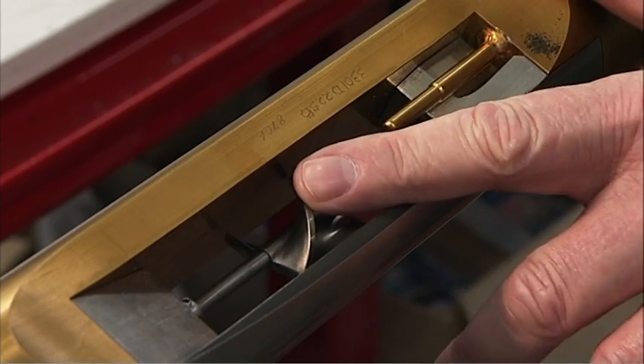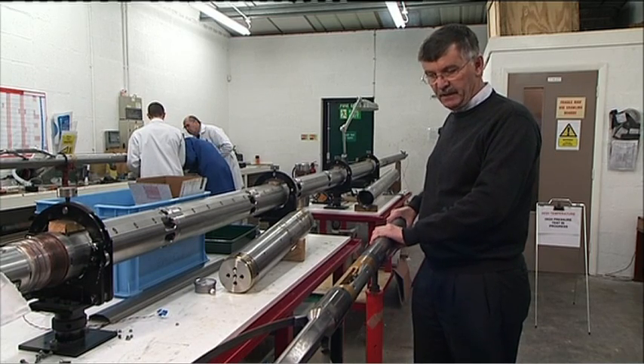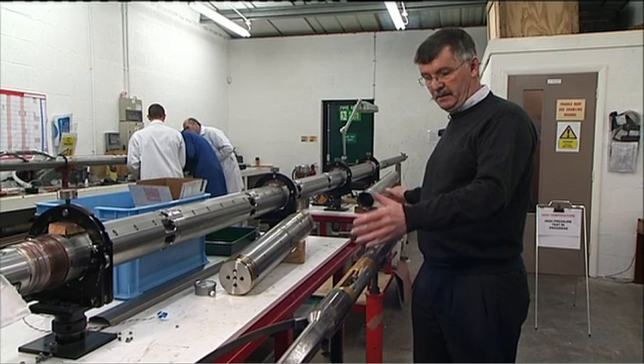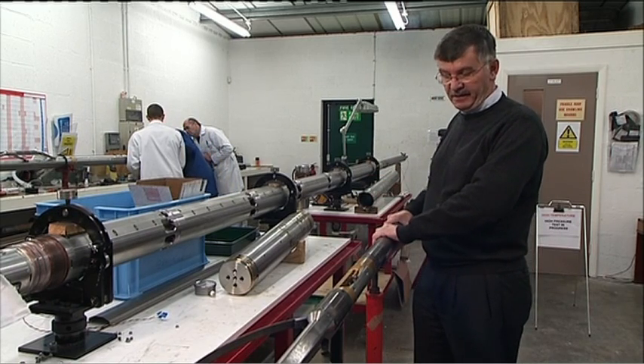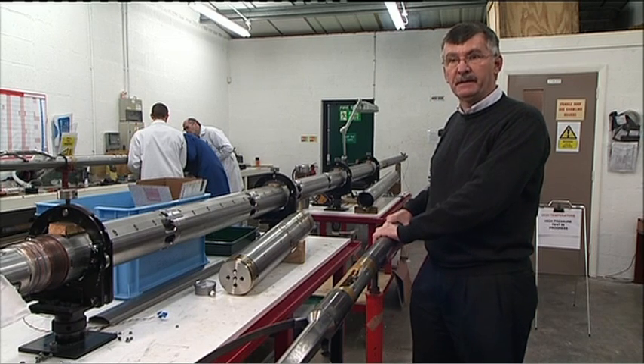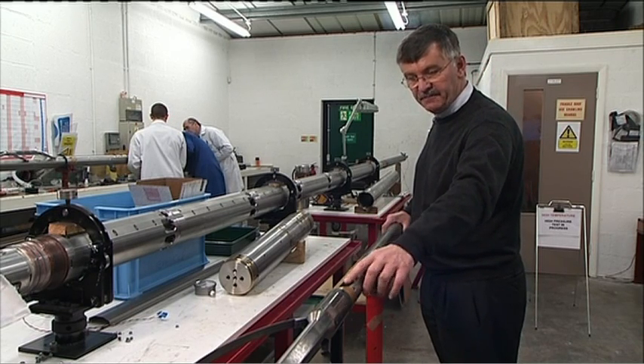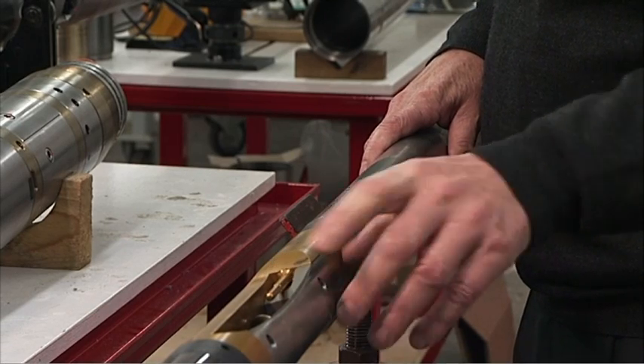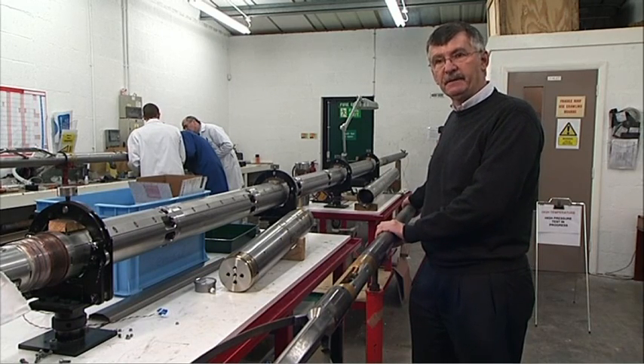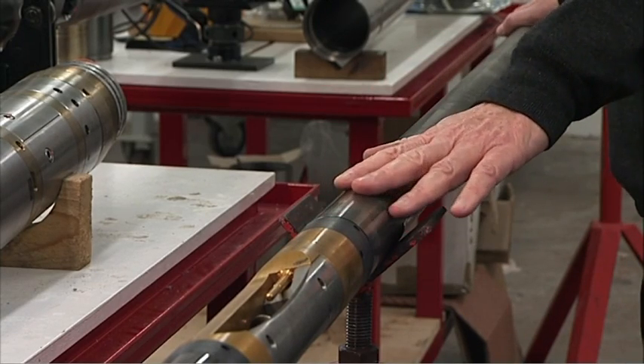This tool consists of various sections. We have a sensor section here, and in this long tube here, we have a heat sink and electronics assembly. The idea is we have a 180 degrees C capable electronic system, but we've wrapped around it essentially an industrial thermos flask. A very special one, and one for us that has been a significant milestone in our technology development. At the front we have sensors for measuring temperature and for measuring flow. We also have a pressure sensor deep inside the tool, and we have an ability to measure changes in magnetic field.